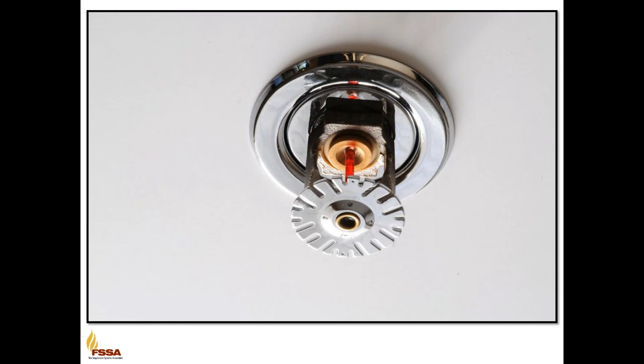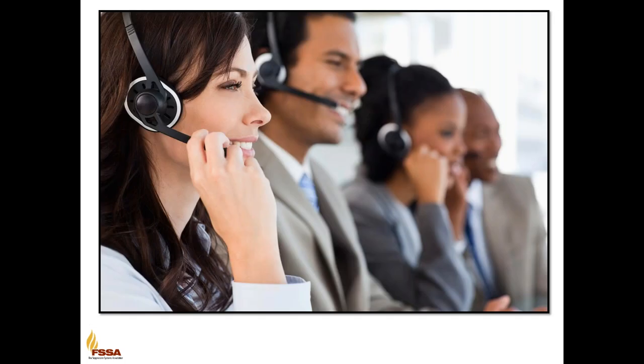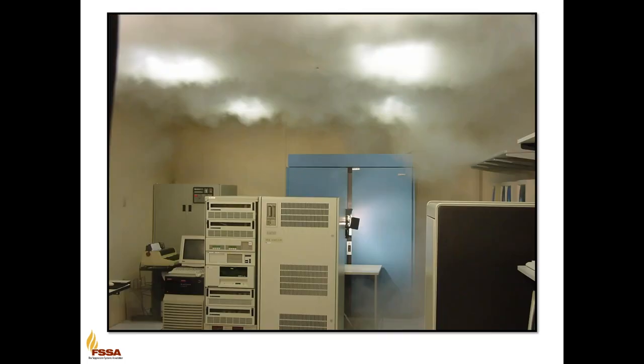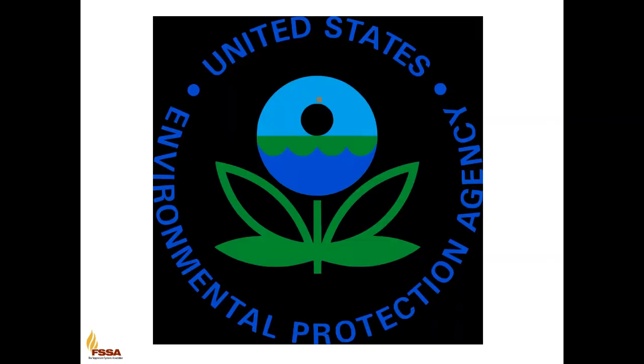operation. Also, halon is discharged as a gas that is non-conductive, leaves no residue, and best of all, it is safe for occupied spaces. It is non-toxic and extinguishes fire at a molecular level rather than by oxygen displacement. If that sounds too good to be true, it was. In 1993, all production of new halon was banned by the United States Environmental Protection Agency and the Montreal Protocol due to its high ozone depletion potential, or ODP.